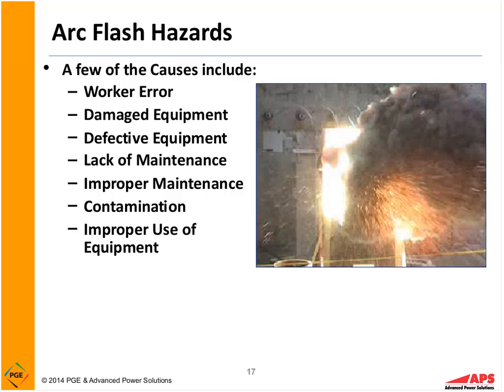Okay? We can have damaged equipment. So that was one of the incidents that I experienced, an arc flash from damaged equipment. We can have defective equipment. Or lack of maintenance sometimes, if we're not maintaining our systems, improper maintenance, contamination. I've got one site where they've had several squirrels get in, and sorry about the illustration, but squirrels and rats and so forth get into the switchgear. Improper use of equipment can also create arc flash events. In my case, the first arc flash event I went through was actually due to an improper installation. It was a poor installation that, after it was discovered, after it caused the arc flash for me, the owner of that facility actually went in and took that installation out and corrected it.